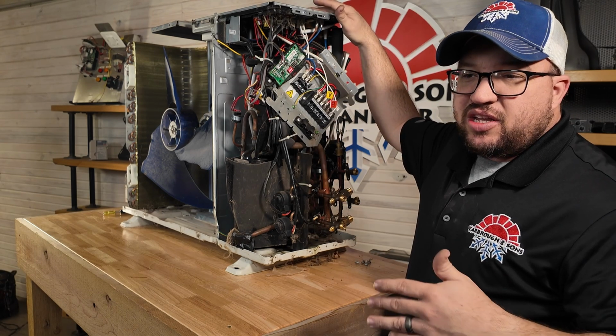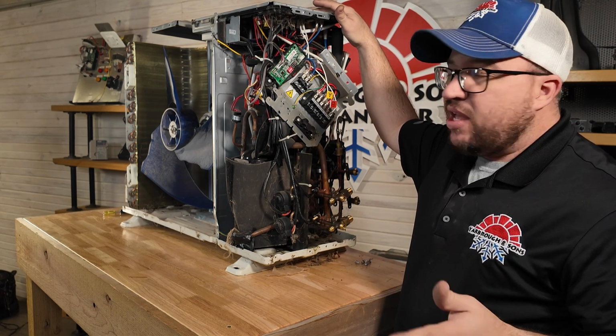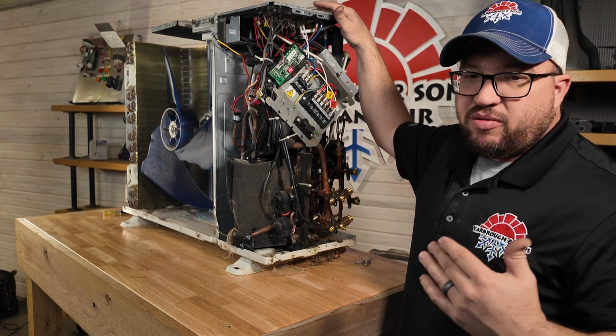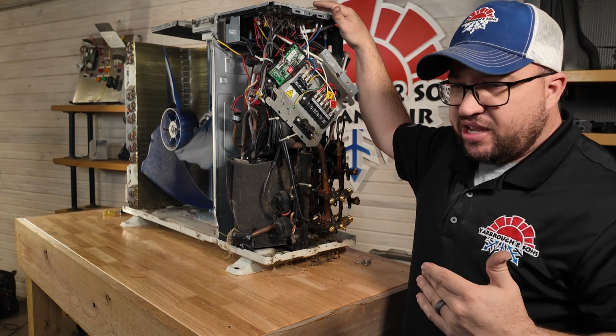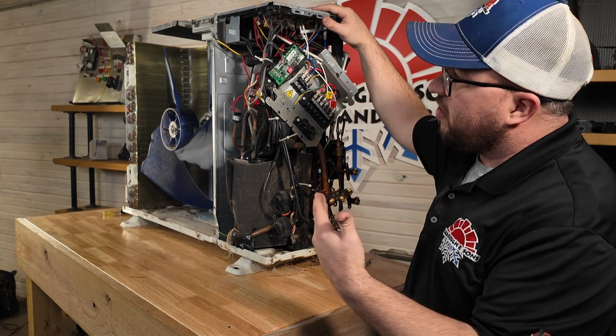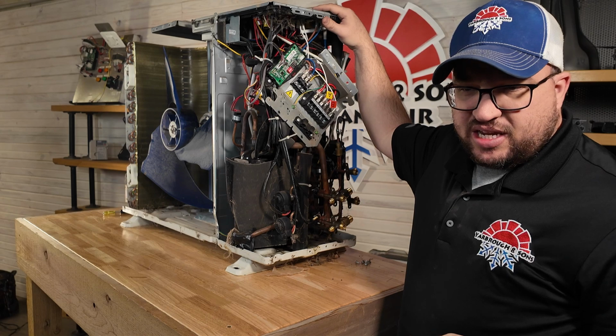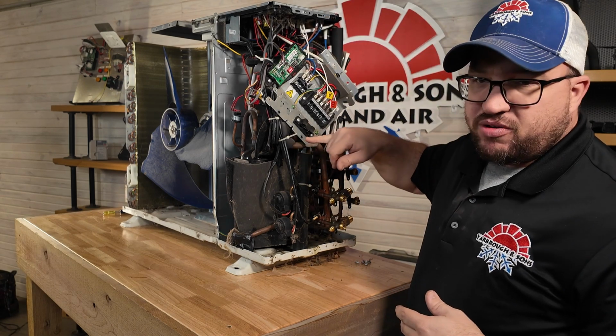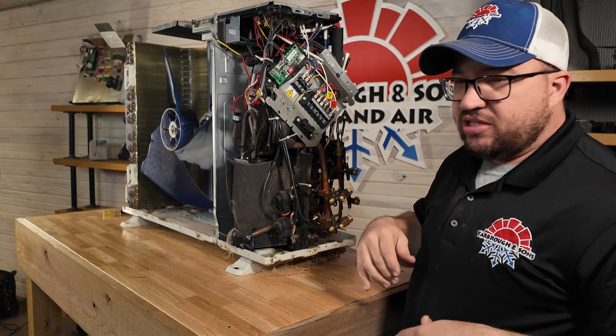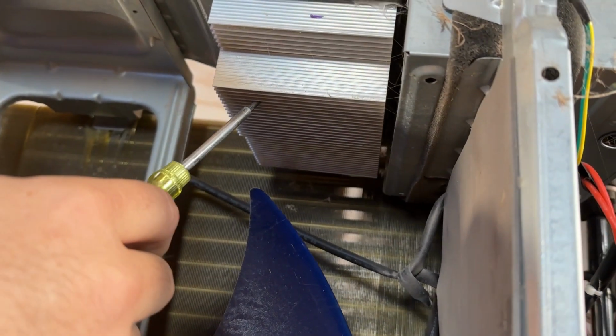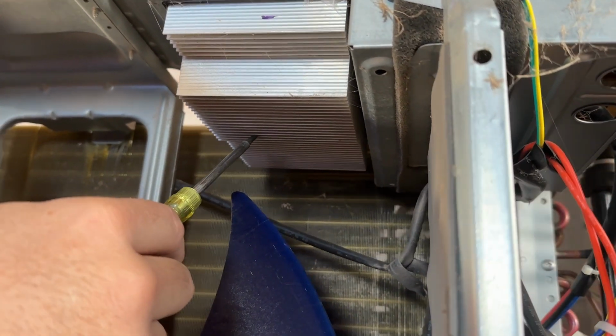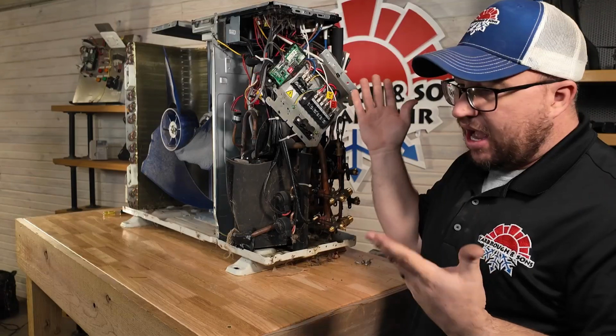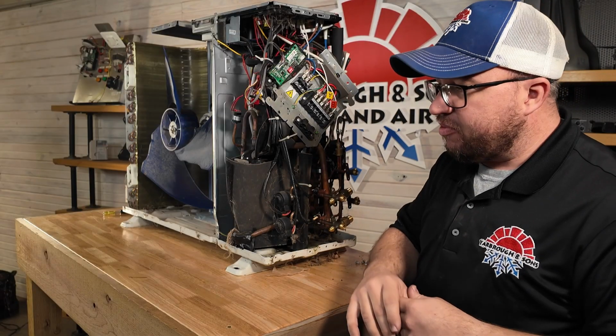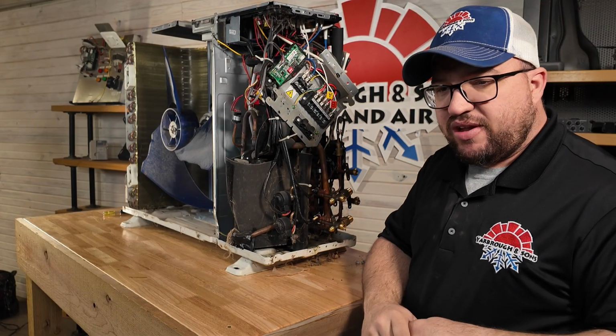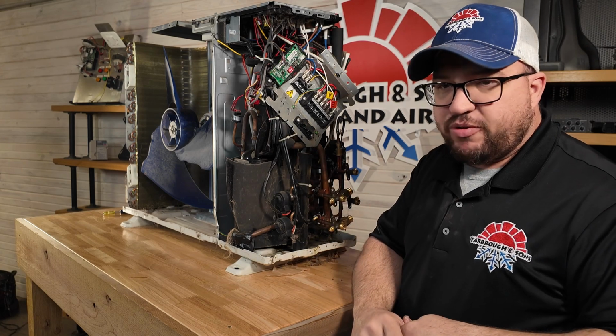Another thing you'll actually see on the IPM is a heat sink. Now systems do it differently - some of them have an air-cooled heat sink, and some actually use the refrigerant line as a heat sink, which is a nice little technology. This one actually uses the air. Air heat sinks have been around forever, I don't ever have any problems with them. I like the air one. I like the other one too, but air's great because all you got to do is clean it off, and it usually works really good.